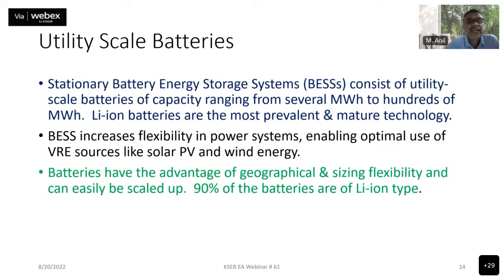Utility scale batteries. A stationary battery energy storage system, BESS, consists of utility scale batteries of capacity ranging from several megawatt hours to hundreds of megawatt hours. And 90% of the batteries in use today are lithium-ion batteries, so lithium-ion batteries are the most prevalent and mature technology in BESS. BESS, battery energy storage system, increases flexibility in power systems, enabling optimal use of VRE sources like solar PV and wind generation.